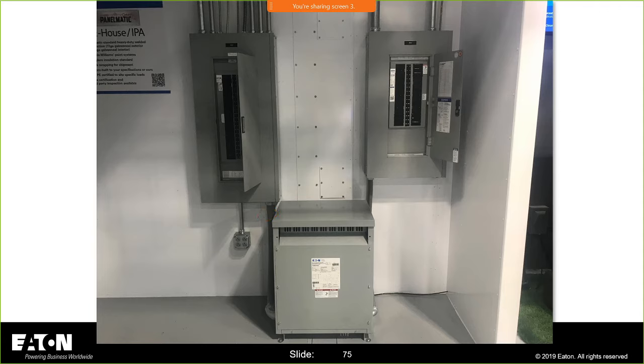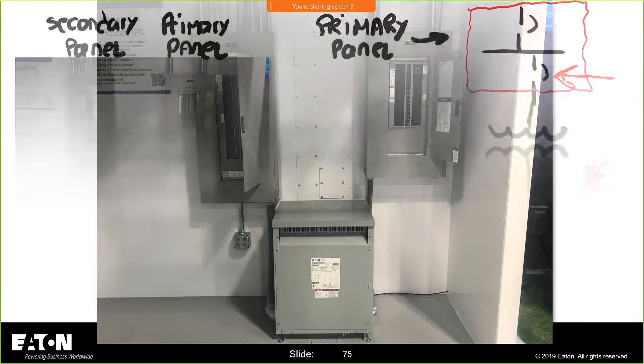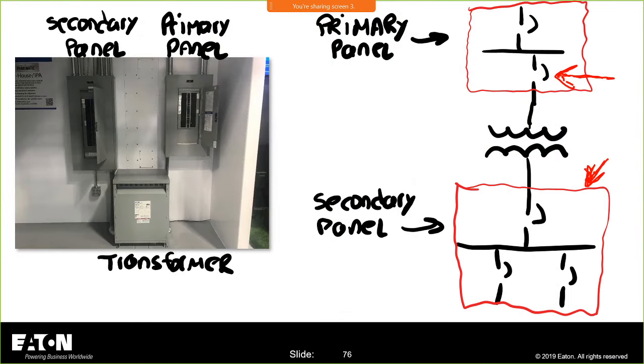But to understand the hazards in this application, I really have to understand that the next upstream overcurrent protective device is the one that's going to be doing the job, right? So if I'm working on this secondary panel board over here, if I'm standing in front of this panel board and working, I can't rely on the main overcurrent device that's in that panel board. I have to rely on the next upstream overcurrent device, which happens to be in that panel board.